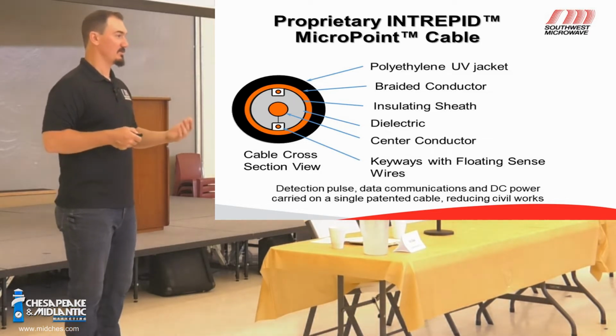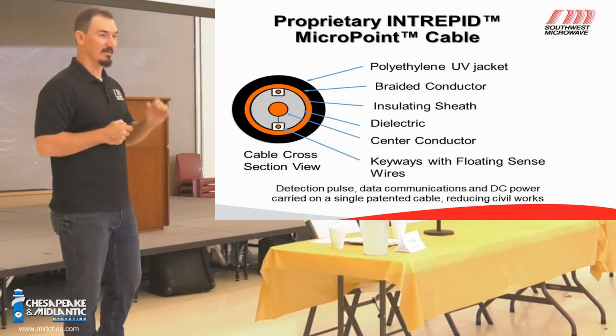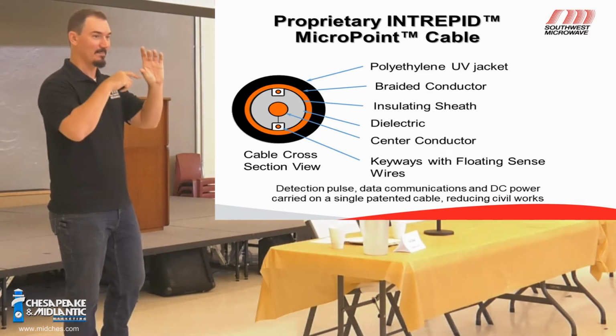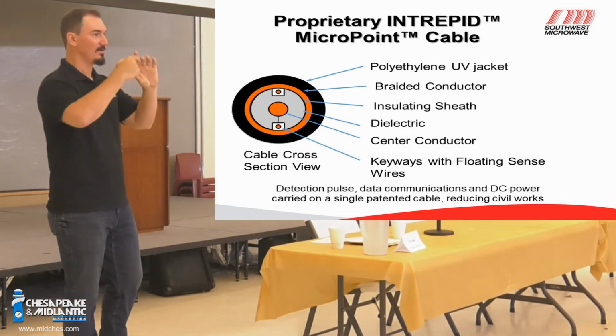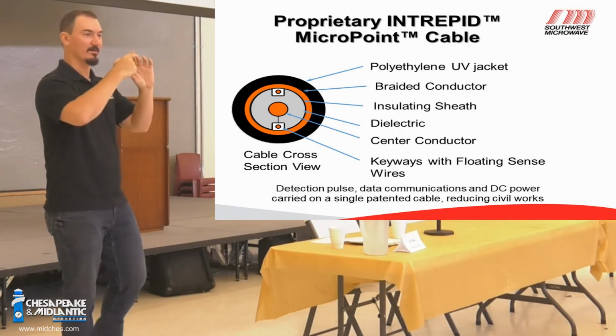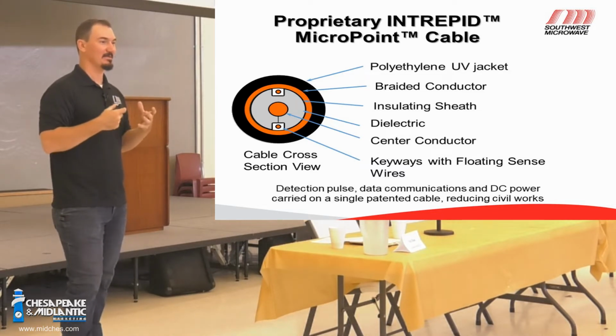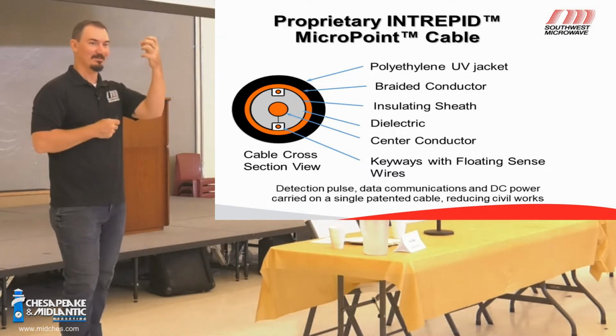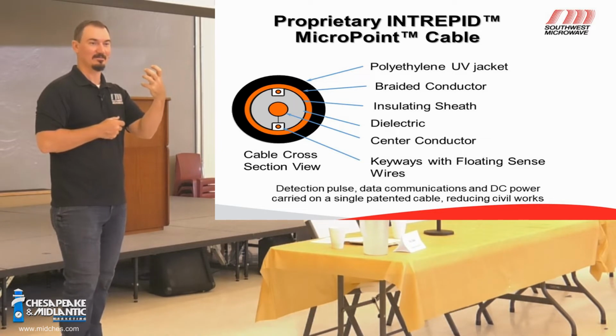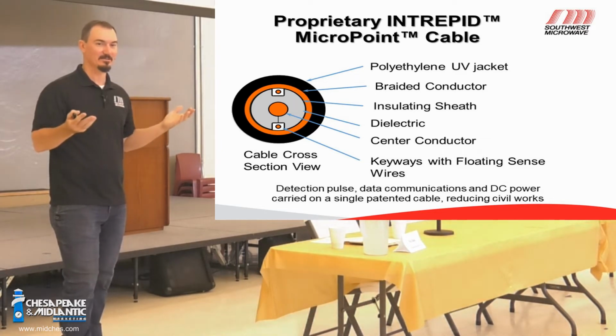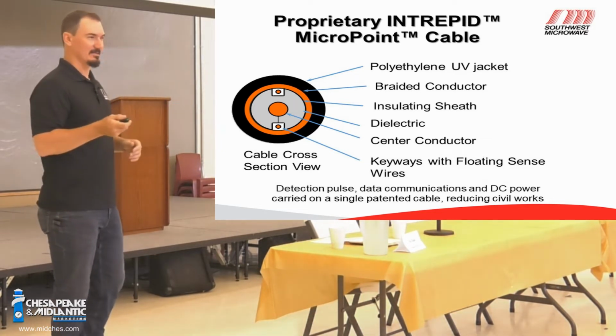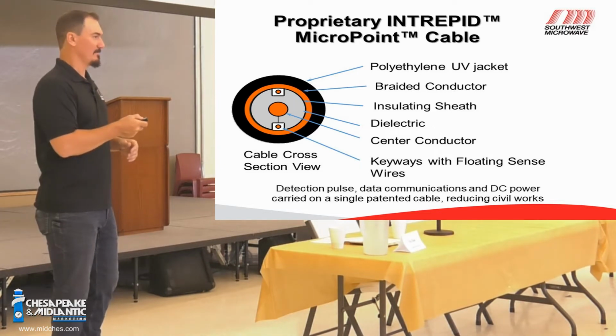So these are things that you can spot check your installers on. You can look and make sure there's dielectric grease going from the outer jacket of the cable all the way up to where the sensor wires are. Because when it does breathe, when it does expand, if they put that dielectric grease on there, it draws that in and it seals itself. Then you don't have to do any maintenance on it for years. Make sense? Okay.